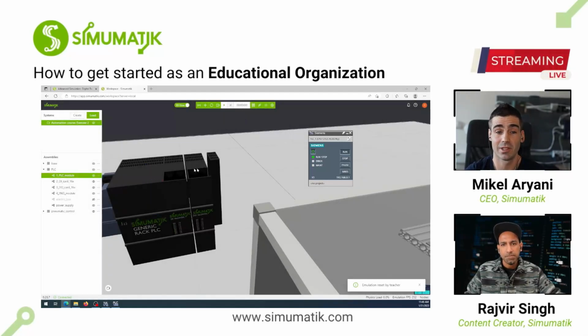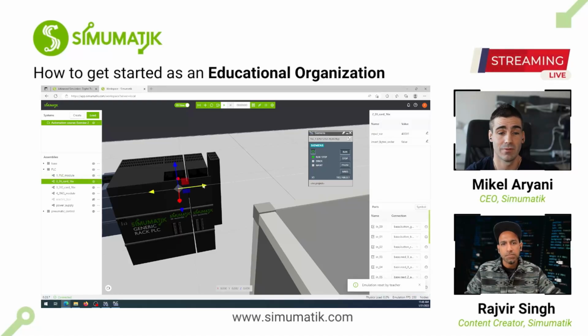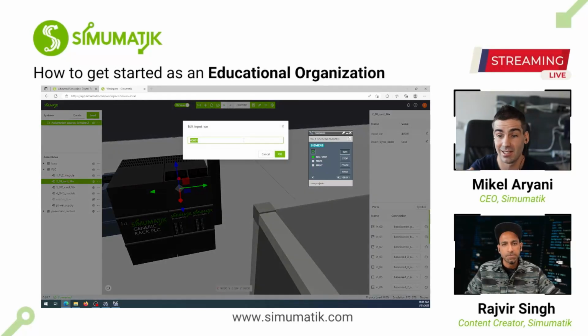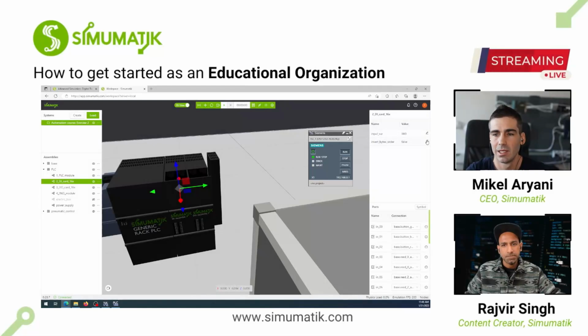This is something that we didn't do before, because we have the cards here, but the addresses where the inputs will be written and the outputs will be read are set up as in the tutorial for Modbus registers. We need to tell this card, this is an input card, let's put 16 digital inputs in word 0.